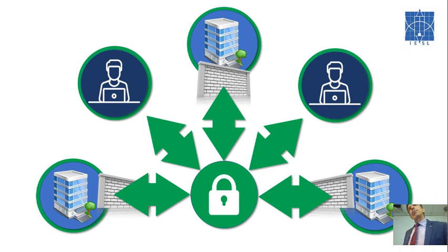You said that a few hacking incidents happened in various countries before. You mean how they got to the controller level, like say you had the BMS running on BACnet, even with a BACnet network? Yeah, there's some. They have gone into that level. The BACnet standard has a port forward, the BACnet port, 47808. So if it's BACnet MSTP or RS485, still, people have the network - people can still get in because it's an open port. So if a BACnet system is left with the standard port open, Shodan can sniff around and find that open port. Shodan will actually go and find any sort of open port on the internet, but if you type in BACnet, it's looking for that actual port number. So yes, there are BACnet systems that are being hacked.